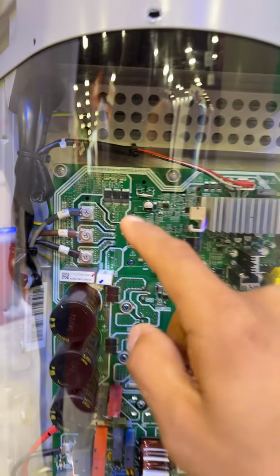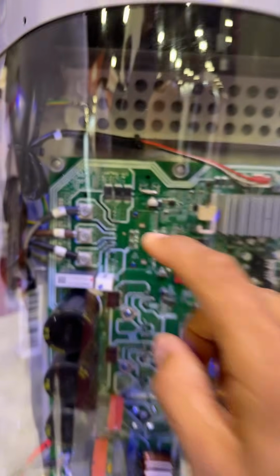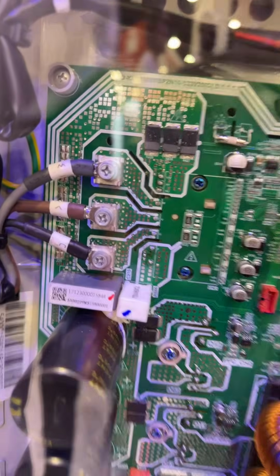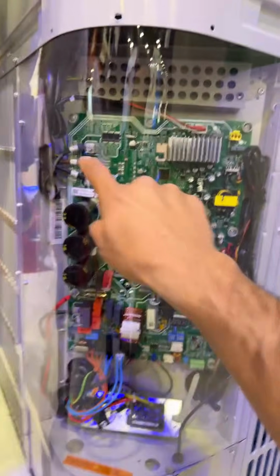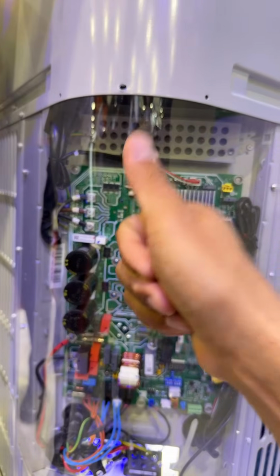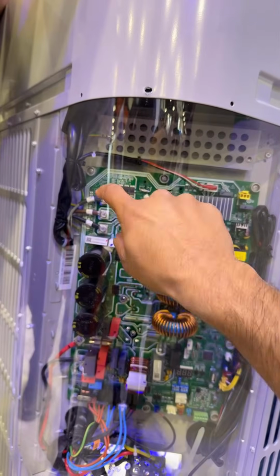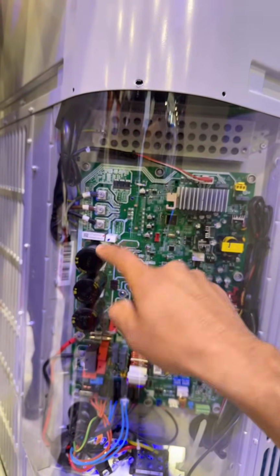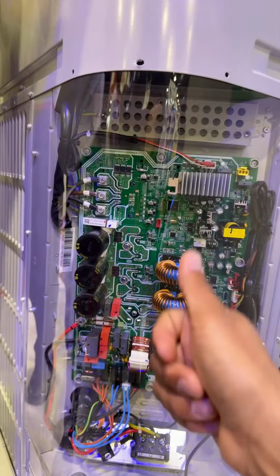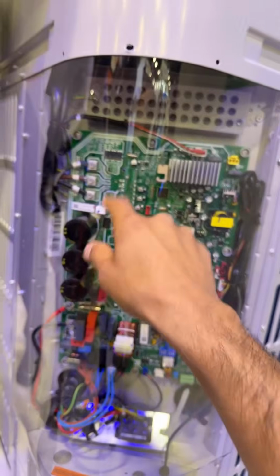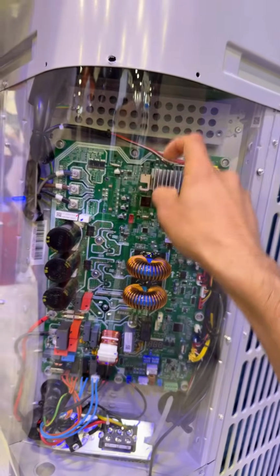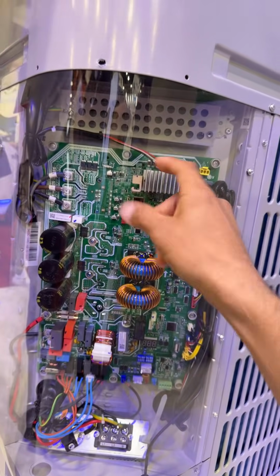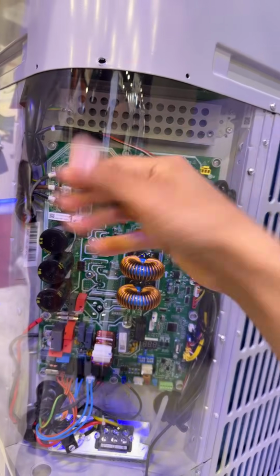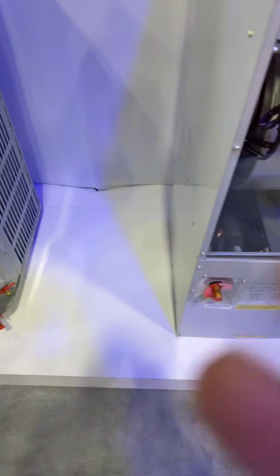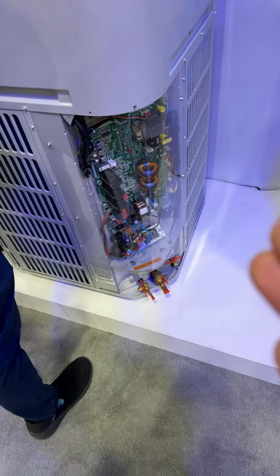Your AC voltage, they don't use run, start, and common. They use U, V, W. So when the compressor's on, you check it on AC voltage, and you check each lead to each other, and they're all going to be reading the same AC voltage. That's how you check these, that's how you check the outdoor fan. If you want to read hertz, you're going to read hertz on each line, they're all going to be the same. So checking for AC voltage and hertz, it's actually not that hard.